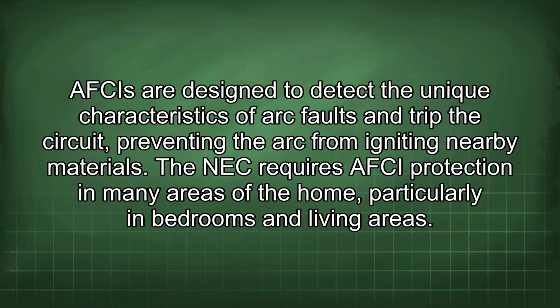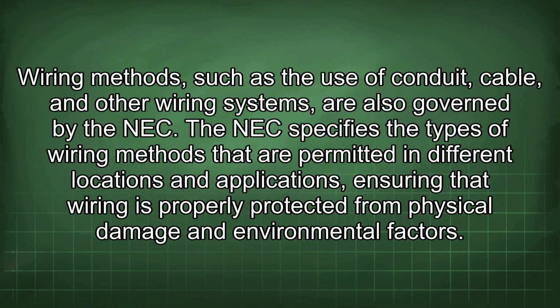AFCIs are designed to detect the unique characteristics of arc faults and trip the circuit, preventing the arc from igniting nearby materials. The NEC requires AFCI protection in many areas of the home, particularly in bedrooms and living areas. Wiring methods, such as the use of conduit, cable, and other wiring systems, are also governed by the NEC. The NEC specifies the types of wiring methods that are permitted in different locations and applications, ensuring that wiring is properly protected from physical damage and environmental factors.